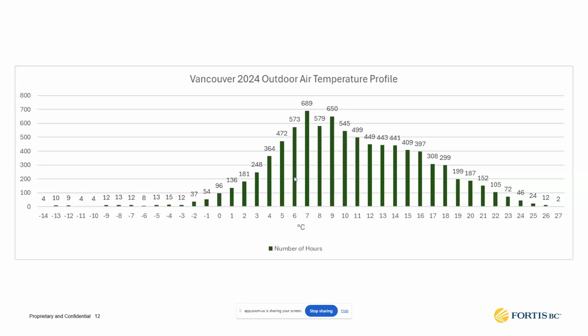This is a temperature profile for 2024 in the Lower Mainland. And this is a typical weather profile, although I don't know if we can call them typical profiles anymore. As you can see here in this graph, these bars are number of hours at different temperatures. The majority of your heating hours, if we're switching over at this temperature, will happen with your heat pump, which is more efficient, and you're going to save on energy. But then at the low temperature, your gas will take over. That means that you will not need to size your heat pump for the lowest day of the year. And this is going to help you with your electrical capacity, as we're going to see here in these examples.